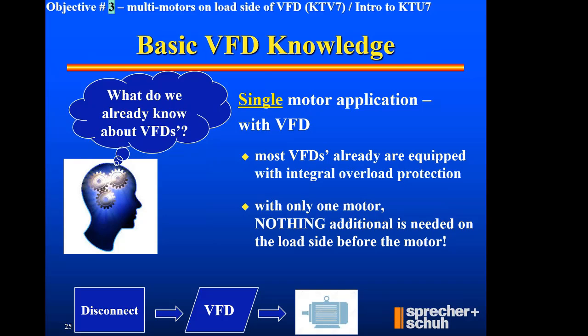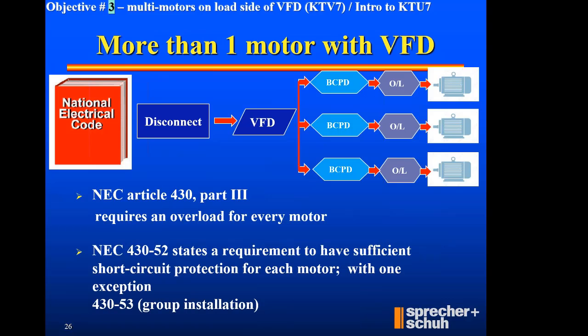Okay, so let's back up a second and say, what is some of the basic knowledge that we know about VFDs already? If it were a single motor on the load side of a VFD, most of them are already equipped with integral overload protection, so not even an overload would be necessary. And with only 1 motor, nothing additional is needed on the load side before the motor, because the branch circuit protection is ahead of the VFD. So if it's not integral with an overload, you're probably going to use a thermal overload. But other than that, today's single motor applications, the VFD is going to take care of all of it.